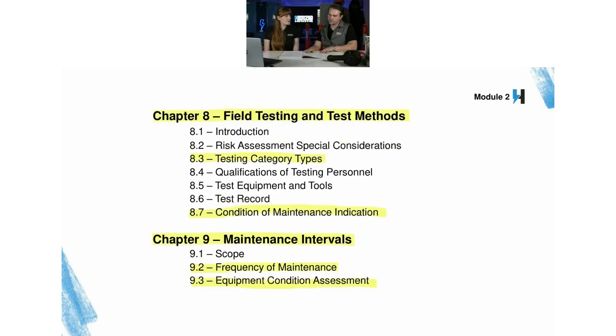Okay, so chapter 8 is field testing and test methods. And something new that's introduced here is testing category types. Yep. So you have categories 1, 1A, 2, and 2A. 1 just means that you can do this testing while the equipment is energized. Yep. 2 basically means that these tests shall only be done while the equipment is de-energized. Right. So they call it online standard tests or online enhanced tests. So the standard test you're going to do regardless. Enhanced test you do if you can't do the standard test, or if the standard test reveals a need to continue on and do an enhanced test. It's kind of the way that we've been reading and learning about this.